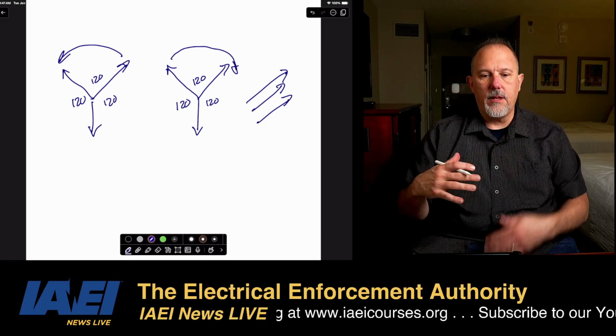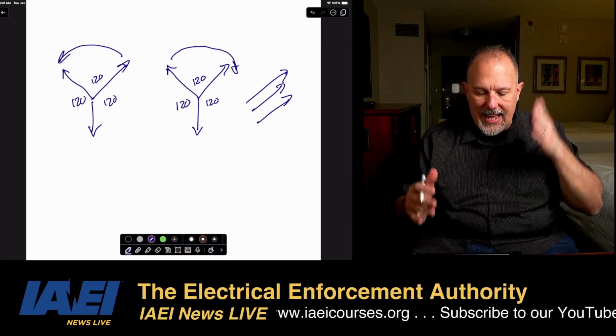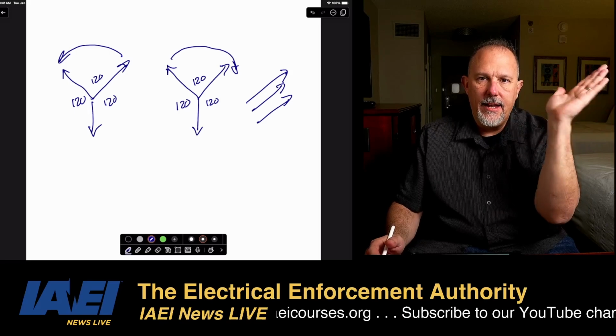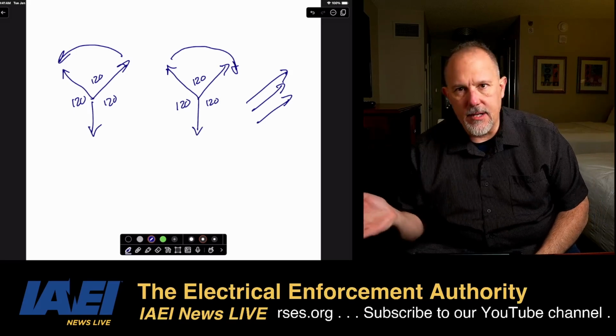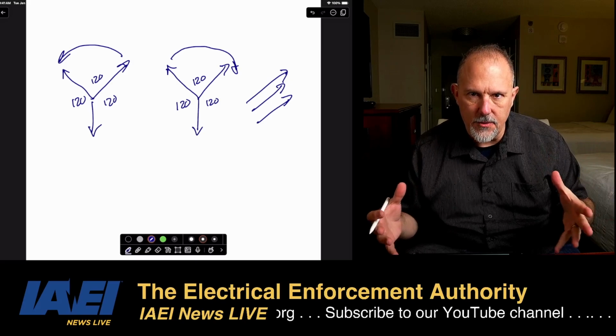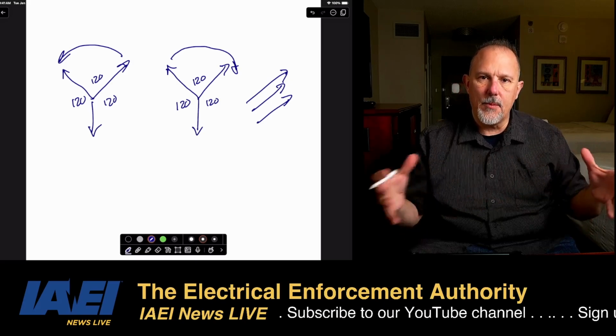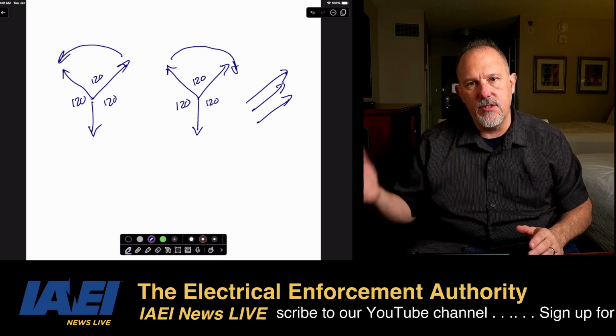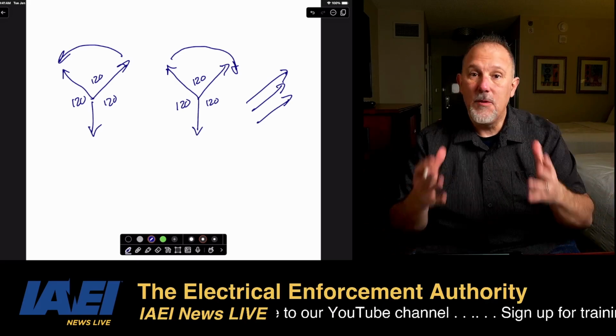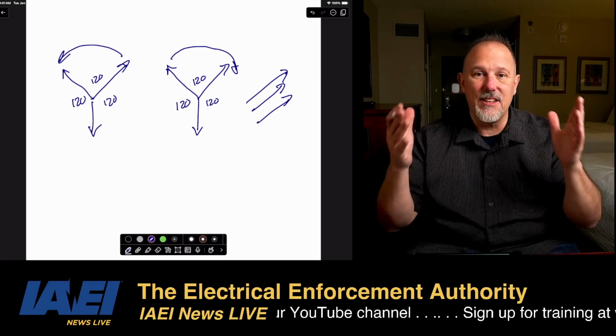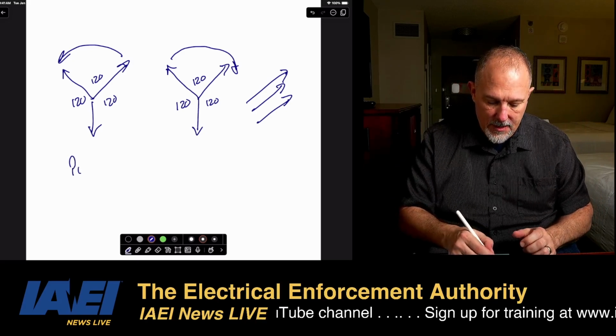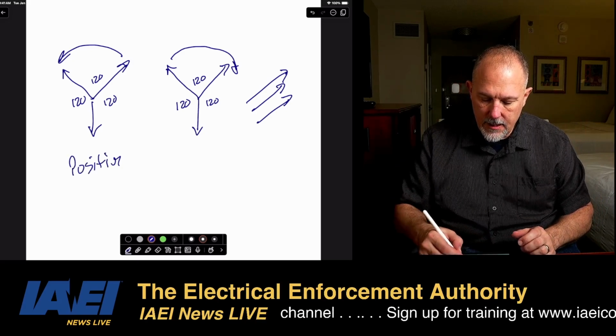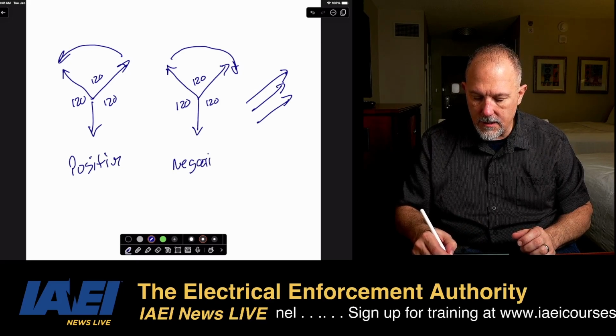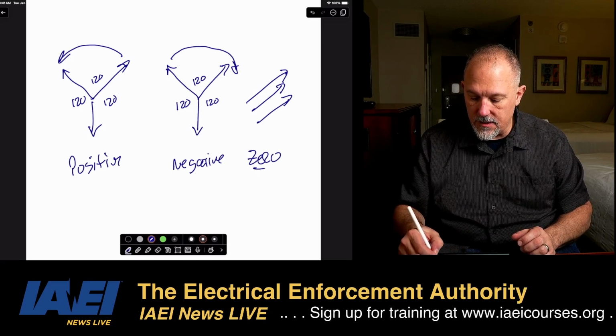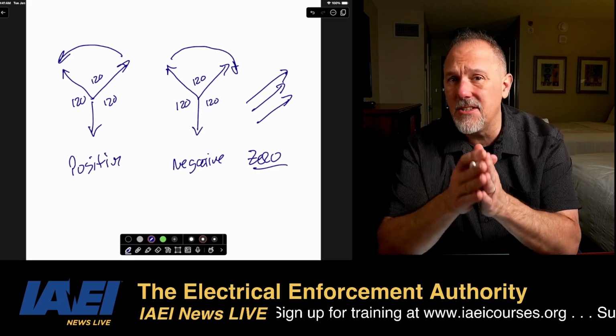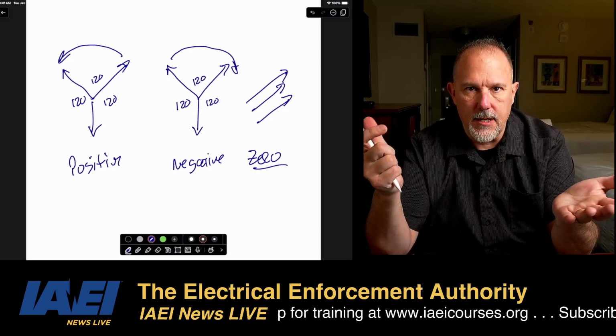So what the math tells us is if I add an angle of negative 120 plus an angle of a positive 120, then they're going to all cancel to zero. So I basically separate my system into positive, negative, and zero, and I calculate fault currents. Your three-phase bolted fault current value is positive sequence. This is positive sequence. This is negative sequence. And this is zero sequence. That's why you'll see the term zero sequence, but you probably have no idea what they're talking about.